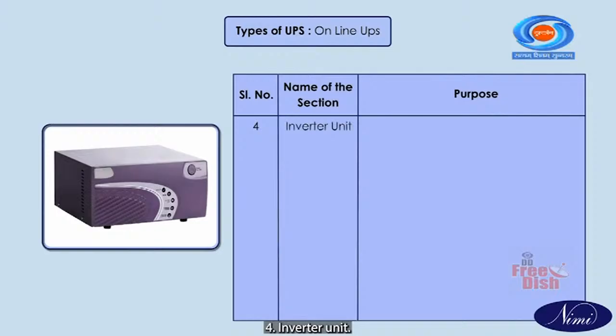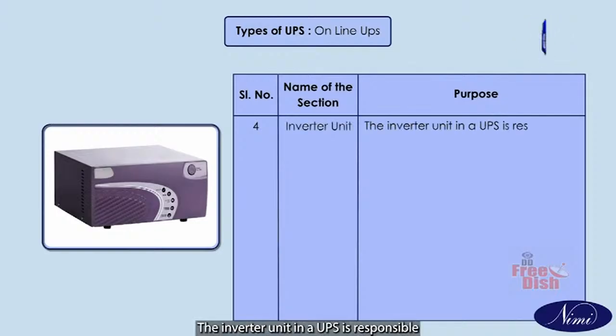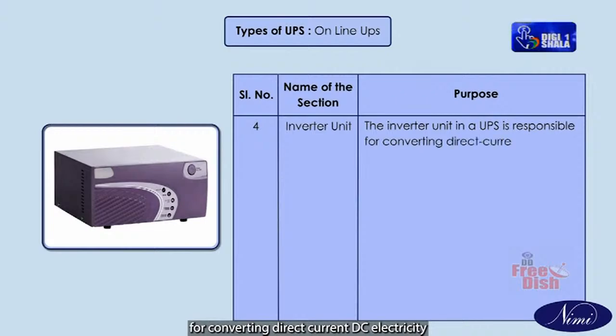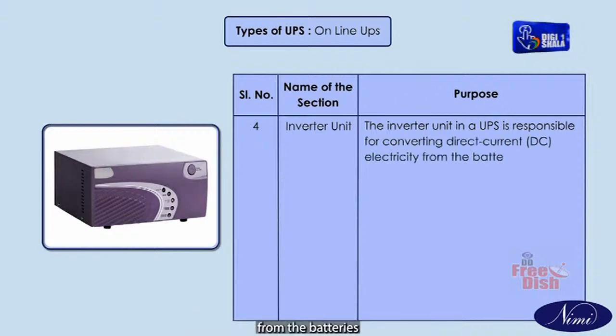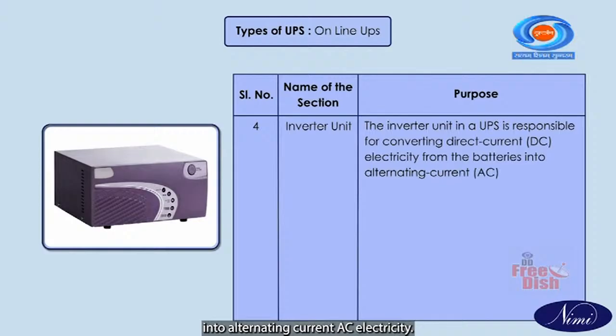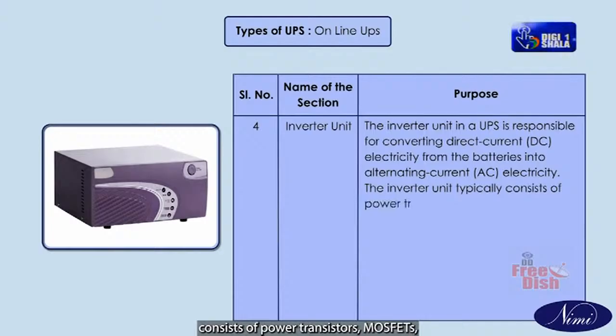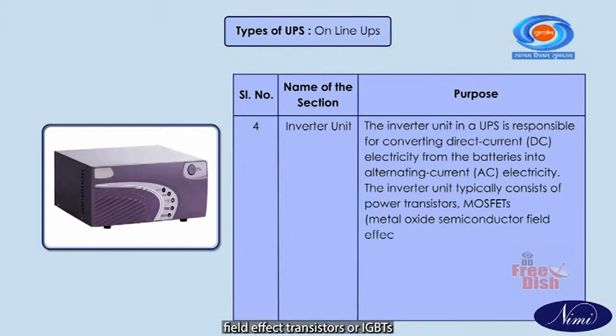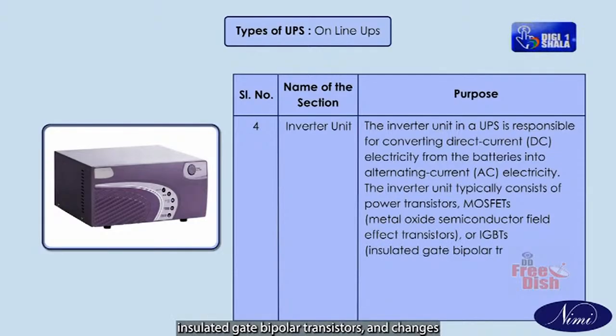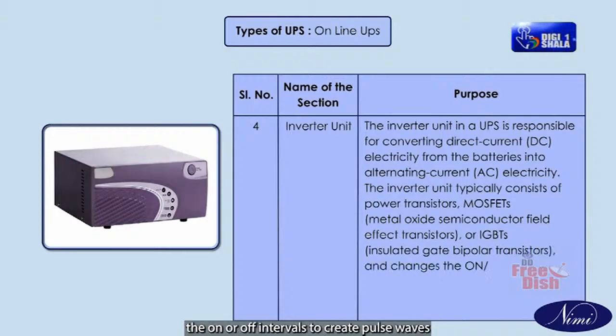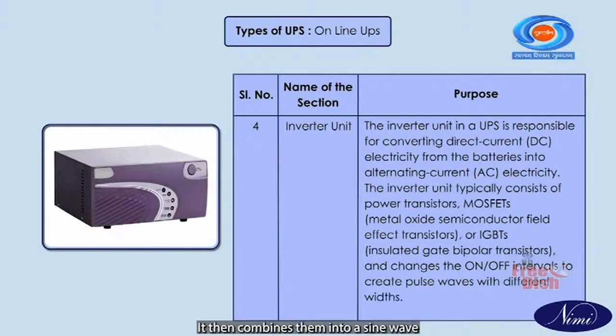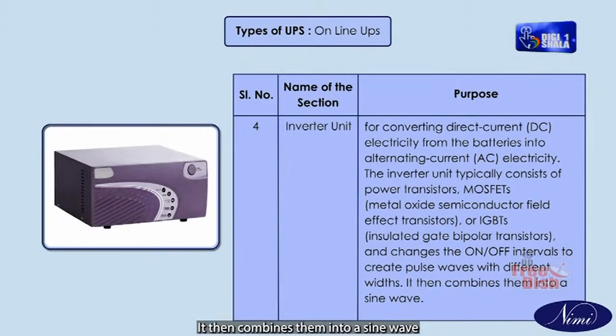Number 4. Inverter unit. The inverter unit in a UPS is responsible for converting direct current DC electricity from the batteries into alternating current AC electricity. The inverter unit typically consists of power transistors, MOSFETs (metal oxide semiconductor field effect transistors) or IGBTs (insulated gate bipolar transistors), and changes the on or off intervals to create pulse waves with different widths. It then combines them into a sine wave.